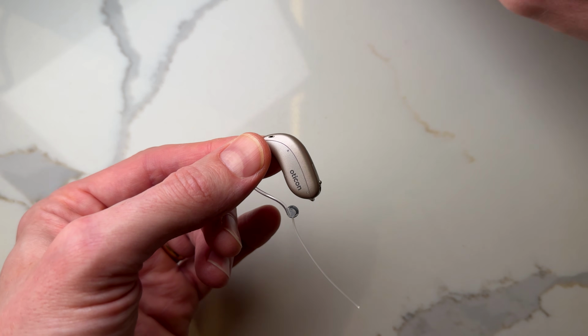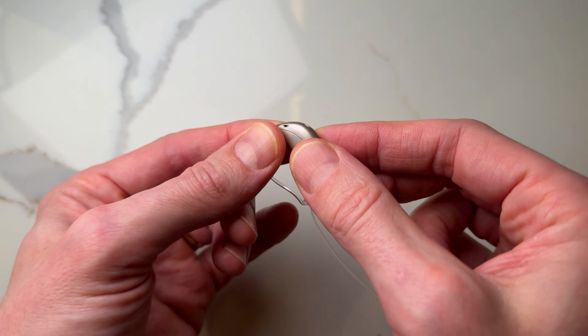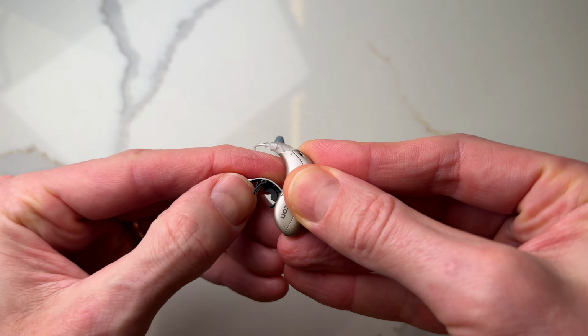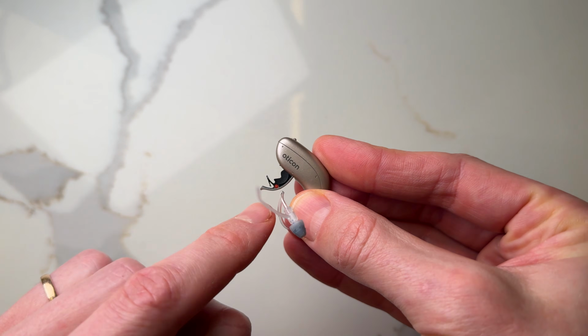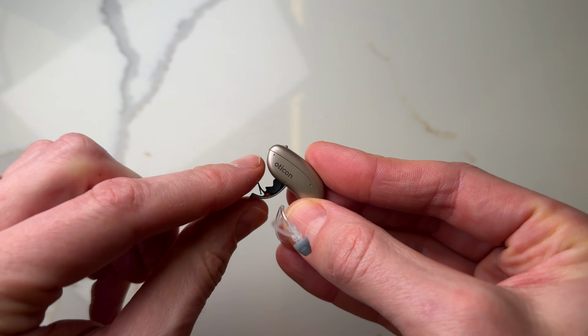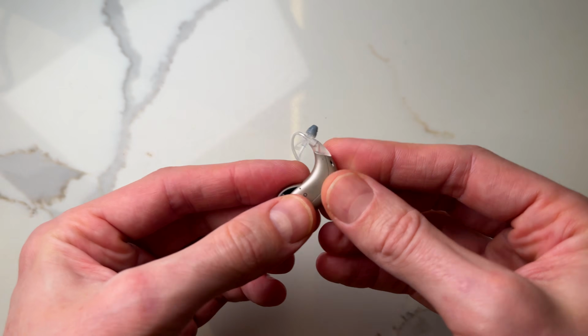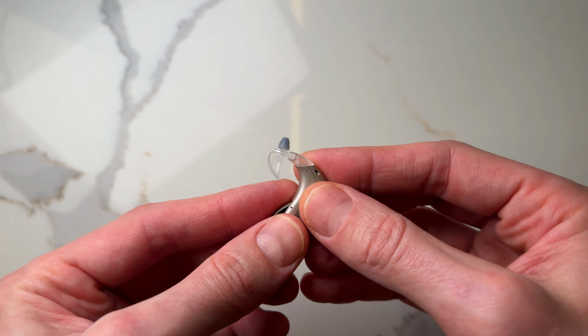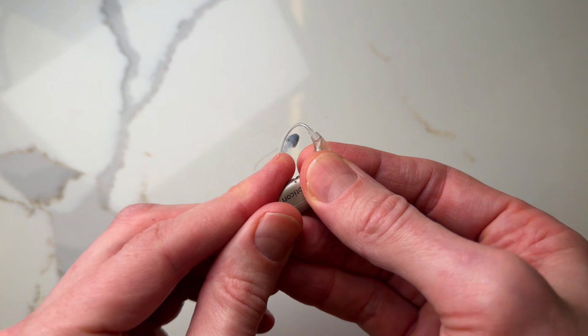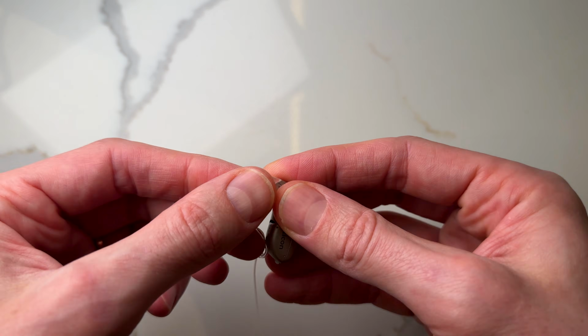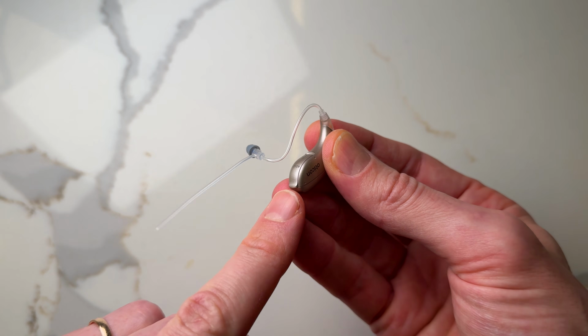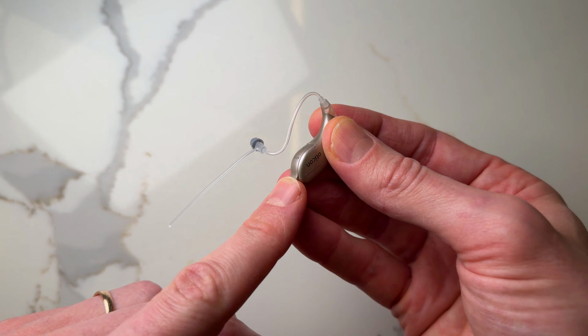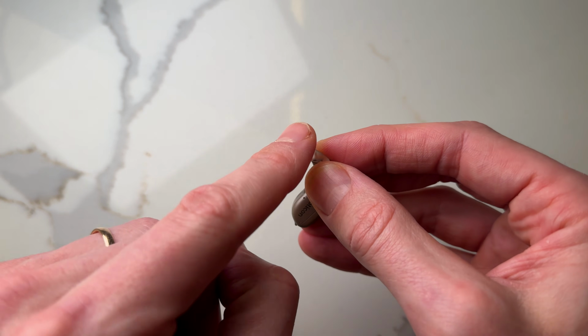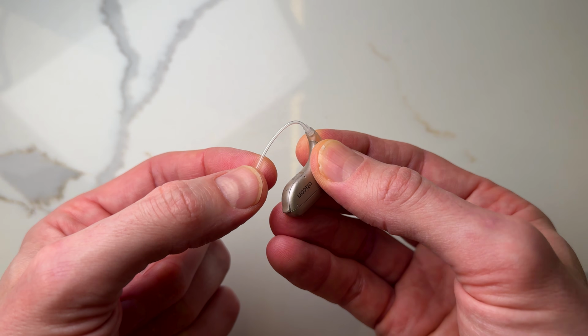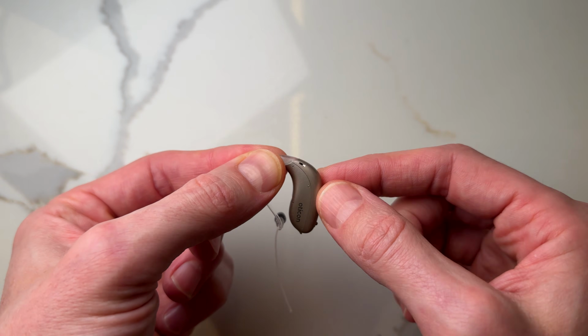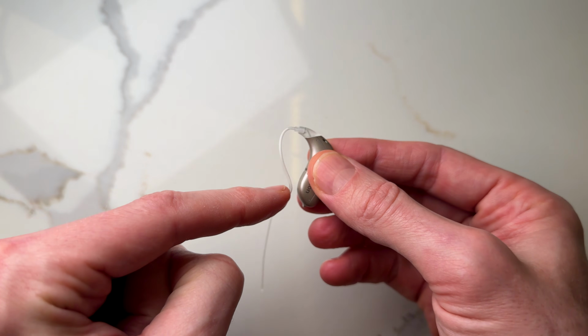Then right at the bottom is the battery door, which houses the battery, and then this coloured marker, which is indicative of whether it's your left or your right hearing aid. Your left hearing aid will show as a blue marker, and your right hearing aid will show as a red marker. Do make sure that you get this right, as you may get the opposite hearing aid in the wrong ear, but it won't stay in for very long. Then if we keep travelling around here, you'll see the slim tube. With this style of hearing aid, the sound is generated within the body of the hearing aid itself and then travels down this tubing into your ear.